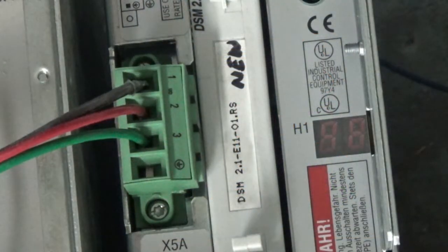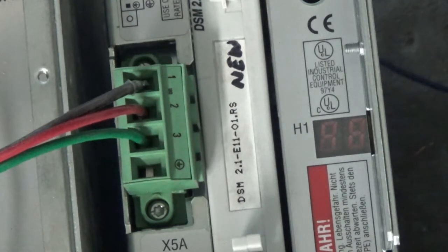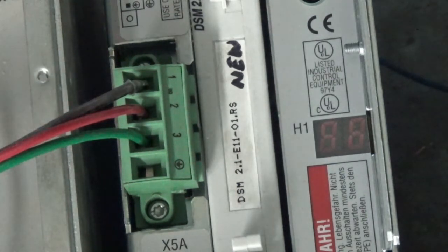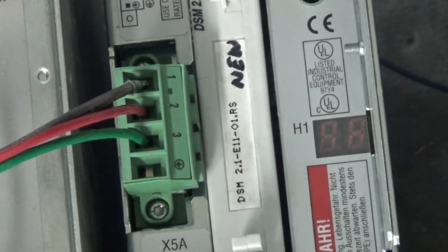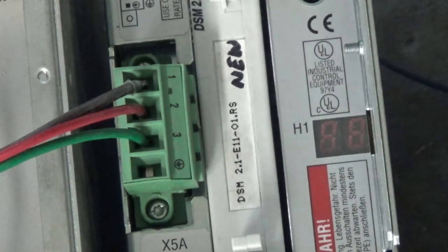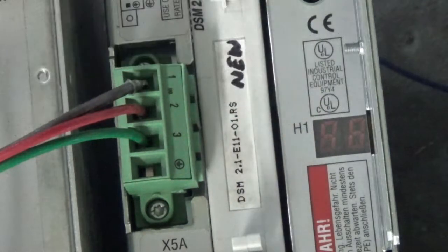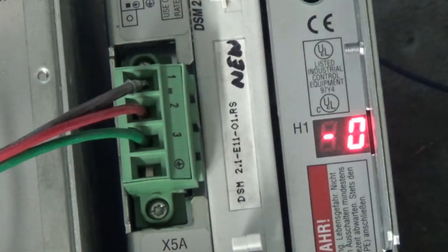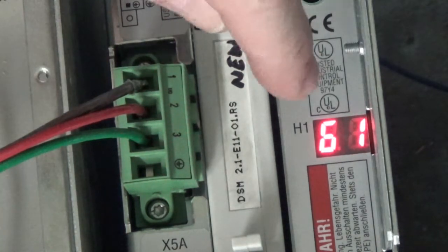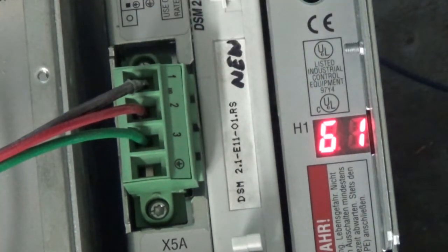Here's an Indramat servo drive, model number DDS-03.1-W030-R, and this servo drive was booting up to alarm 61. Overcurrent, short to ground. Let me power it up. Watch this display right here. There we go. Alarm 61. We're going to have to fix that.